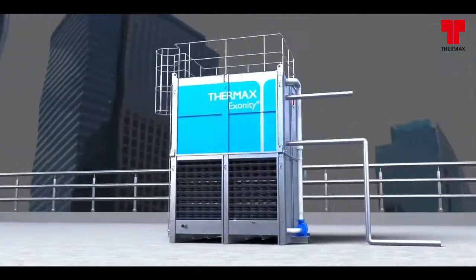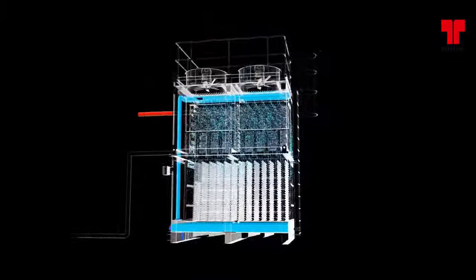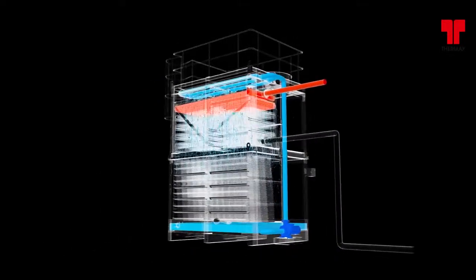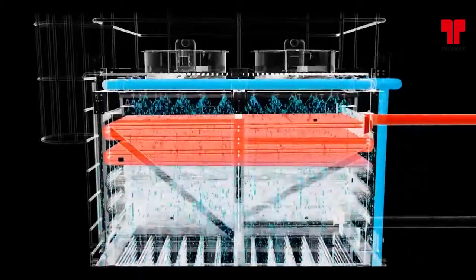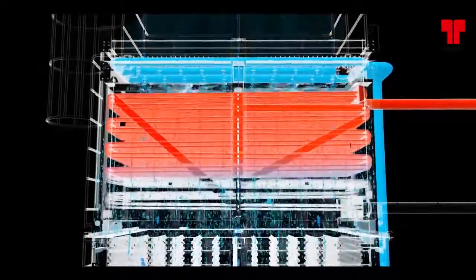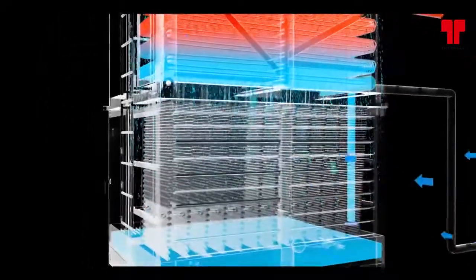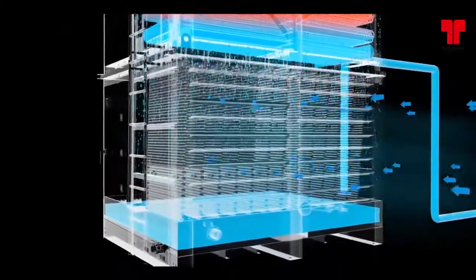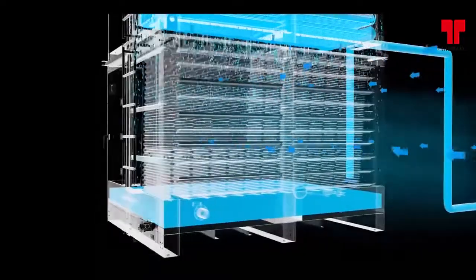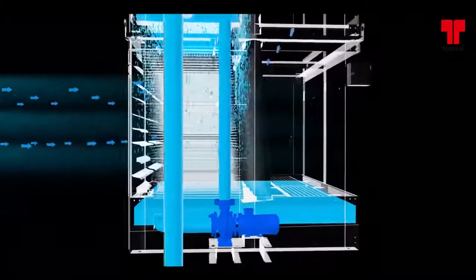In this type of EVC, the refrigerant is circulated through the coil of the evaporative condenser. Heat from the refrigerant is dissipated through the coil tubes. The heat is removed directly by the downward natural induced air, aided by a spray of water cascading over the tubes.